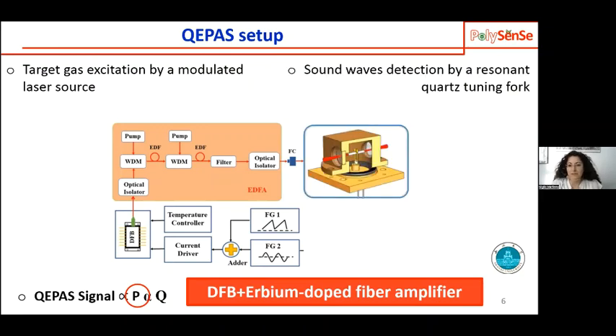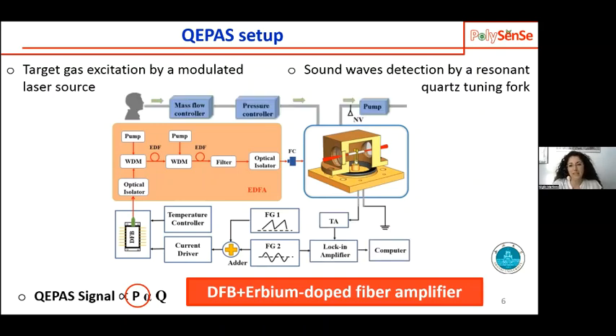The laser was focused within the acoustic detection module, and you can see here the quartz fork coupled with the two microresonator tubes, which aim at amplifying the acoustic wave. And here you can see the gas sending system. So the patient can breathe through the system, and flow and pressure conditions are controlled.